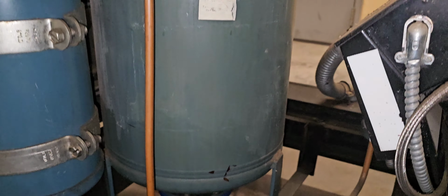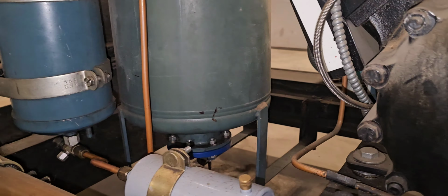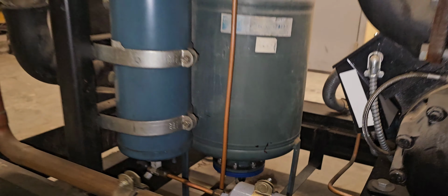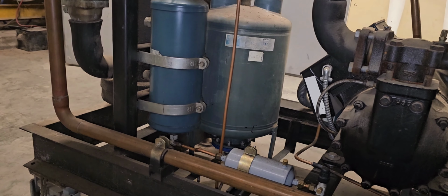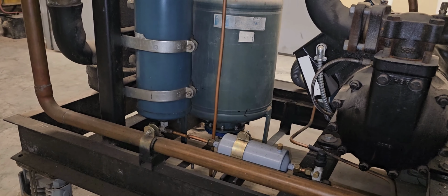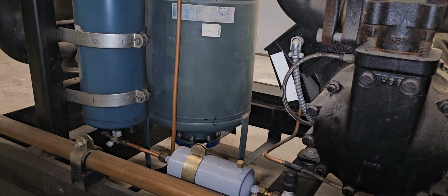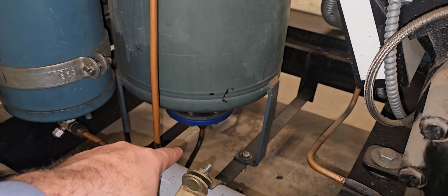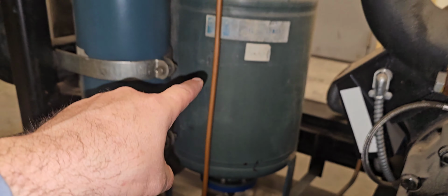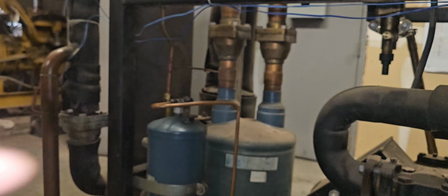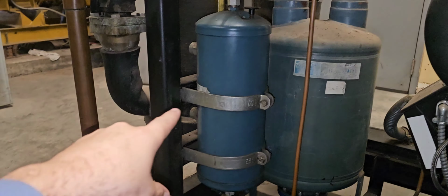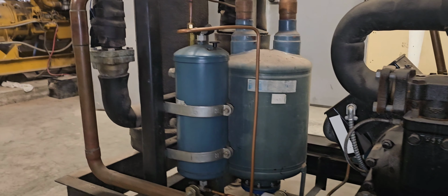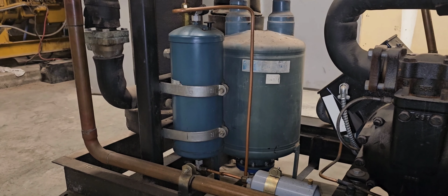And then on the bottom of this, you've got a float. If you take that off, you're gonna have a ball float. If anybody's familiar with carburetors, it's the same exact thing, a ball float in a carburetor, where you have a ball and a needle valve. And you can see there's a line coming off of the bottom of this separator that's coming up and going into your reservoir. So this is where the biggest difference between a high pressure and a low pressure oil system is.